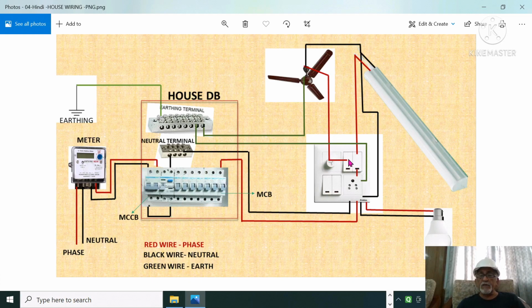Take this connection direct to the switch and put it on. If the fan starts working at high speed, that means your regulator is damaged. So change this regulator — first put off the MCB.